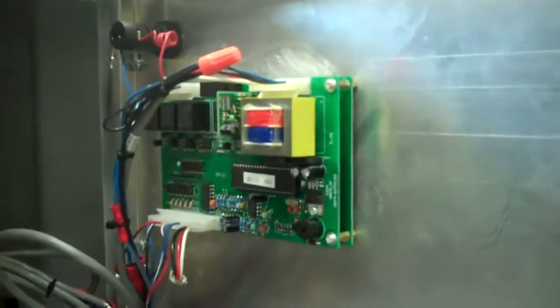Open up the cabinet. And we have our compressor contactor and overload, fan, and pump. That's our transformer for controller power only. That's single phase, taking one leg of the 460 volt, stepping it down to 220. Single phase, that's our controller. We also have the same ID tag information inside the controller door here.